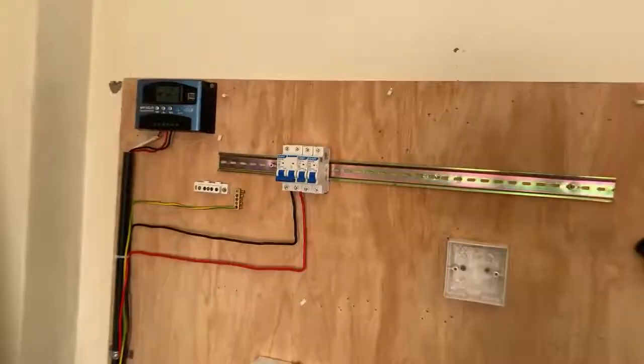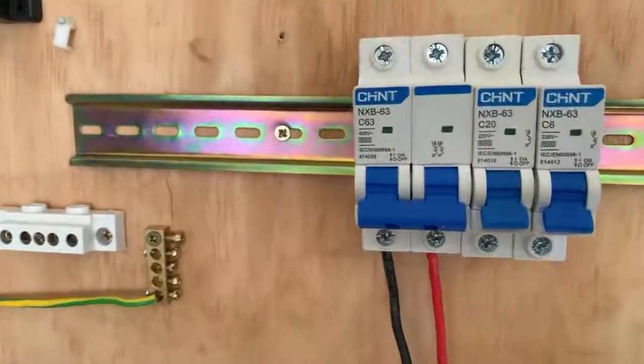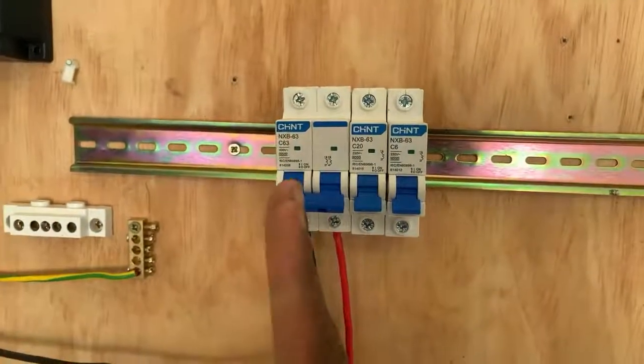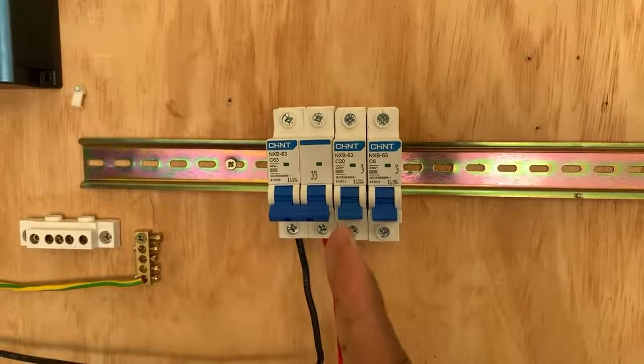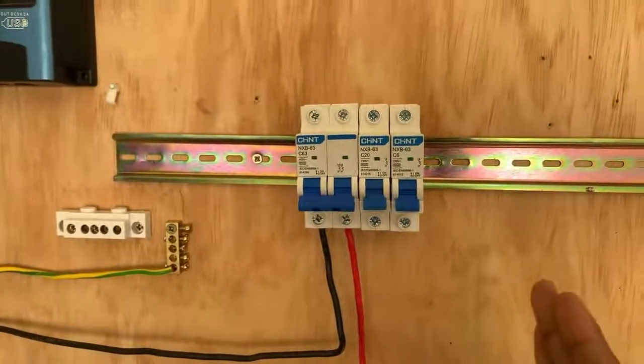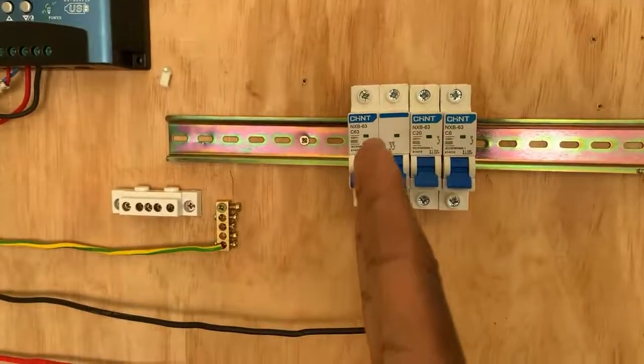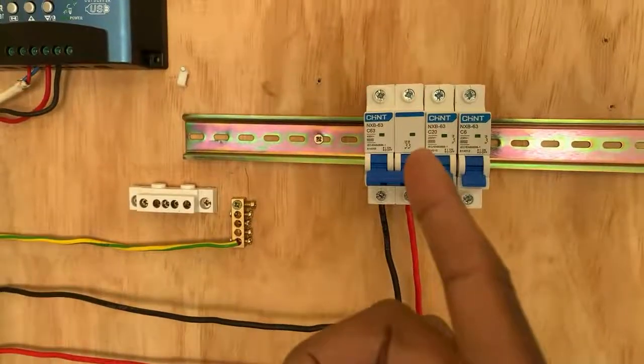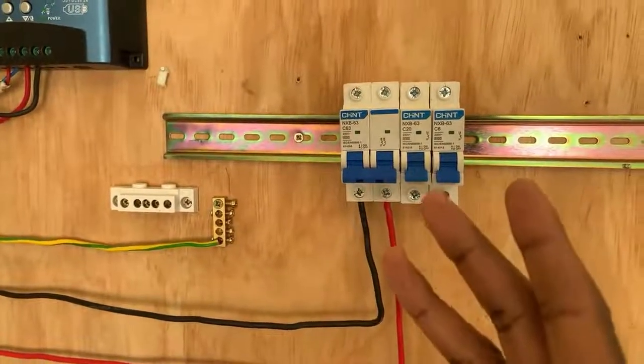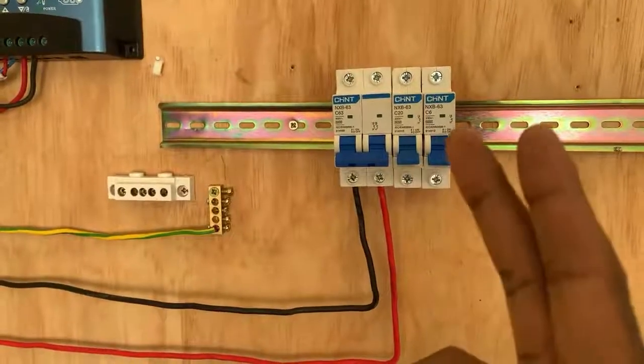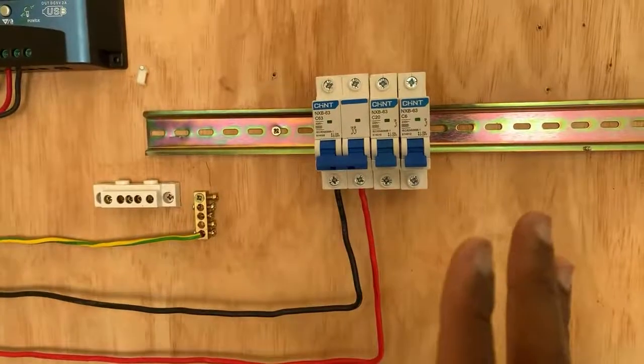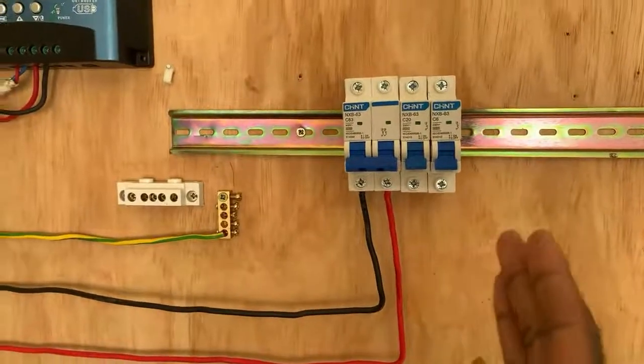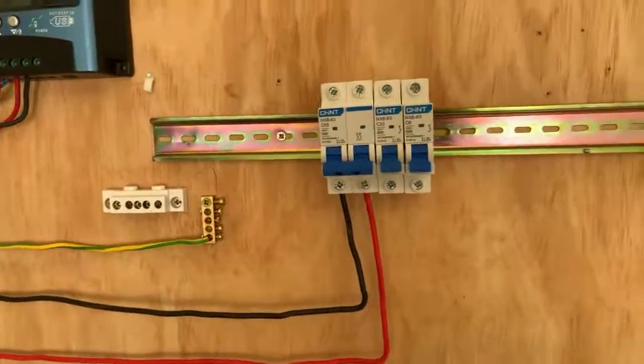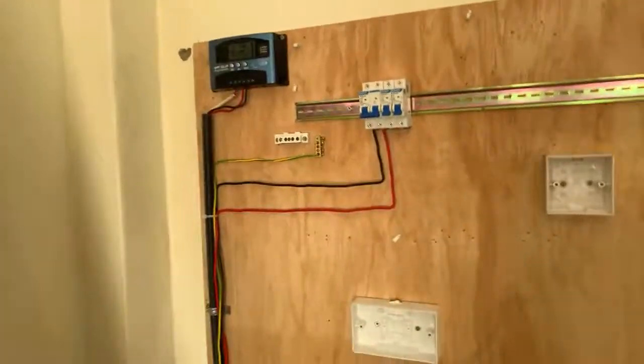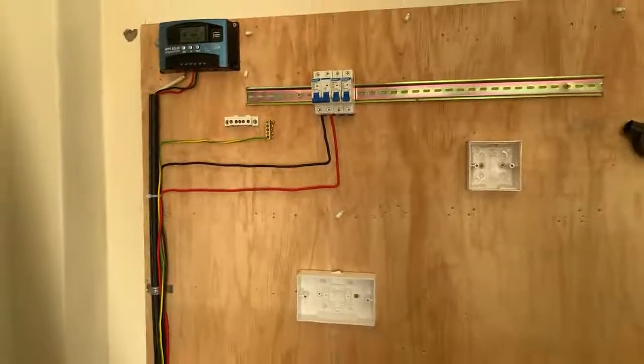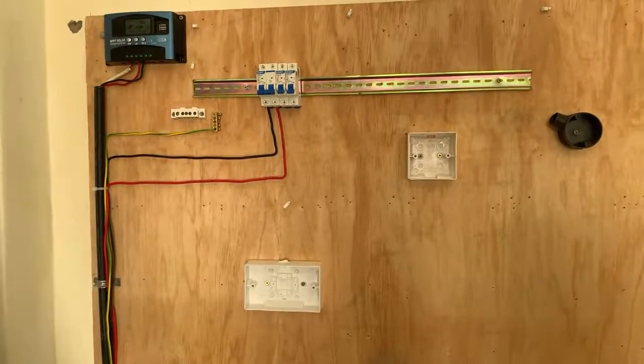So this is what I mean: when connecting them, ensure there's an order where you have the double pole, then the larger one, descending that way. If we had a 32, it would be next to the DP MCB, followed by another 32 if present, then a 20, then say a 10 and a 6. That's how you set it up. Don't mix them so you have a 20, a 32, a 10, a 6, a 5 randomly. No, you put them in order so it's easy for someone to interpret and know that this was done by a person who knew what they were doing.